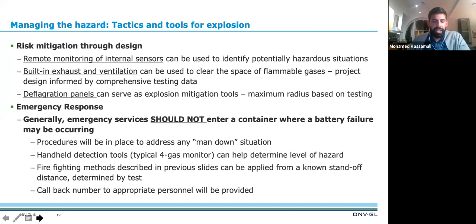For emergency response, emergency services should not enter the container when a battery failure may be occurring. Increasingly, systems are less occupiable walk-in containers, so this is less of a concern, but for instances where there is a walk-in container, no one should be inside. Procedures will be in place for any man-down situation, and handheld detection tools, typical 4-gas monitors, would be used to detect gases and better understand the effects of this gaseous volume.